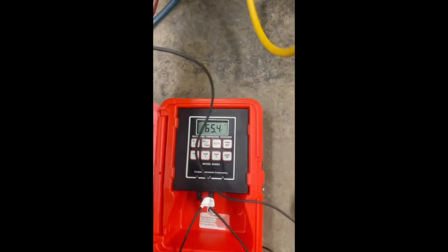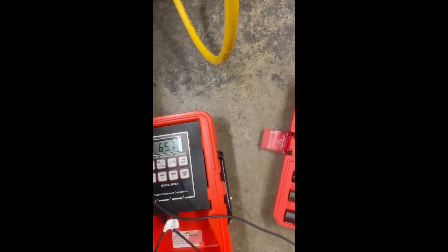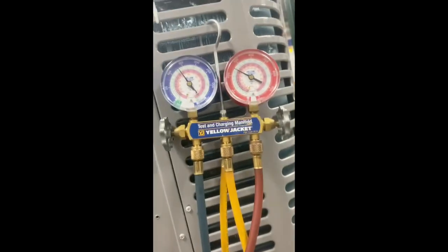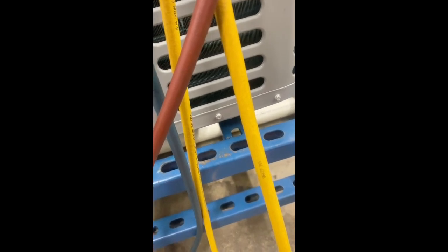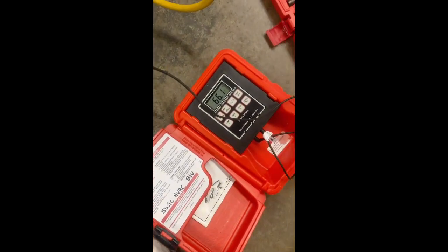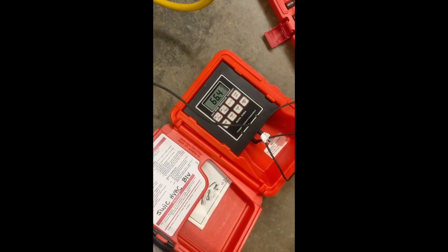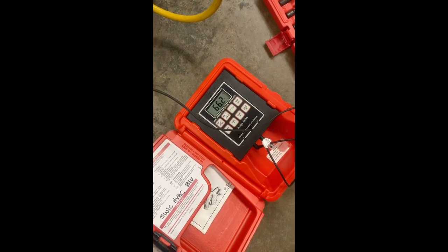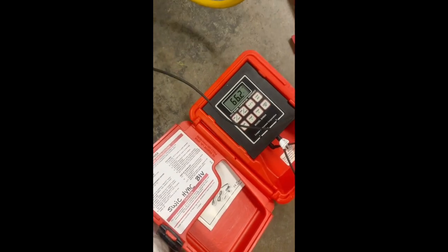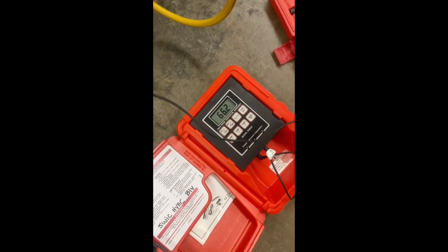So what I'm doing now is checking my temperatures. This is kind of crazy because on this temperature scale, I guess, I'm not seeing much of a difference on either side. That's because I was using line 1 on the temperature gauge when I needed to use line 2. So I'll probably cut this and come back to show what it's actually looking like—this is the wrong probe, the wrong temperature probe, yeah.